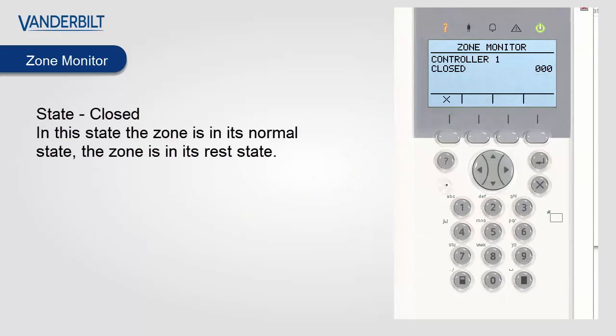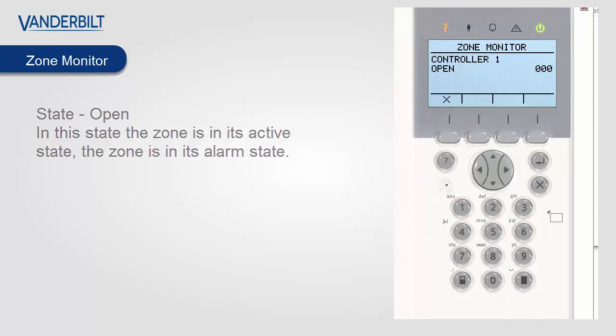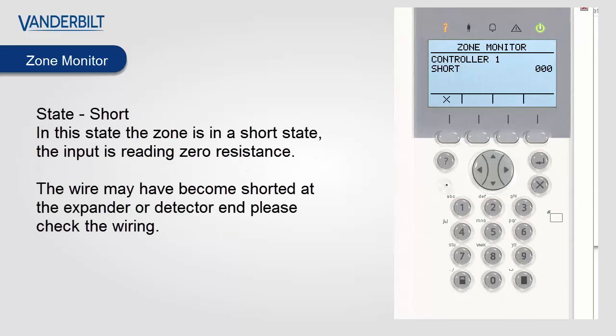Now let's look at some of the different states. State closed is the normal state for a zone — it is in its rest state. When a zone is open it is in its active state and the zone if armed would cause an alarm. The disconnect state means the input is reading an infinite resistance; the wire may have come disconnected so we advise checking the wiring. State short means the input is reading zero resistance; the wire may have become shorted at the expander or detector end, so please check the wiring. Note: a disconnect or a short will trigger a tamper condition on the SPC system.